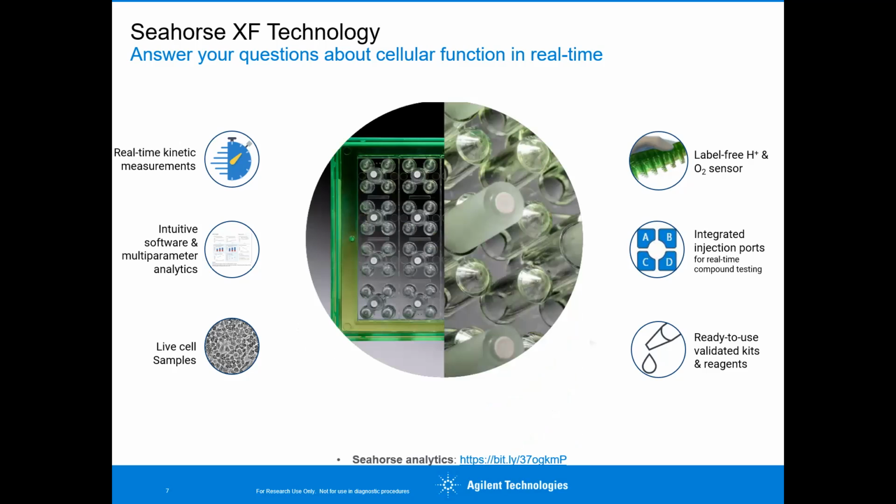And so one more point about the 4 injector ports I just mentioned. You see a close-up of the sensor plate here and 4 ports. I think this rather understated capability is, like I said, understated. It really allows for limitless combinations of experiments. Nearly every single type of cell or sample type: primary cells, cell lines, bacteria, platelets, organoids. And then you multiply this by the various compounds that you can inject, and then the programmable nature of those injections, and you can see the incredible variety of experiments that you can perform.